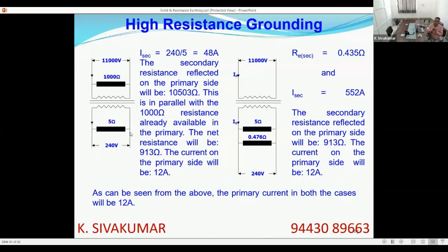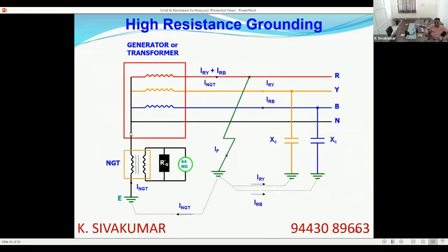Suppose you provide a 1000 ohm resistance on the HT side, the 11 kV side, rated for 11 kV. An 11 kV, 1000 ohm resistor will result in a fault current of 12 ampere. Whereas if you see the diagram on the right hand side, I am connecting only a 0.476 ohm, 240 volt resistor on the secondary side. This also results in 12 ampere fault current on the primary side. So the advantage is you connect an NGT and provide a very small value resistor across the secondary terminals of the NGT. You get the same effect as connecting a very high value resistor on the primary side. So instead of going for a direct high voltage, high value resistor, you go for an NGT, neutral grounding transformer, the secondary of which is connected to a very low value resistor.